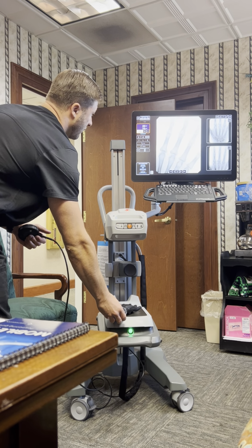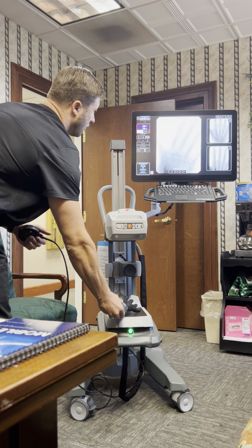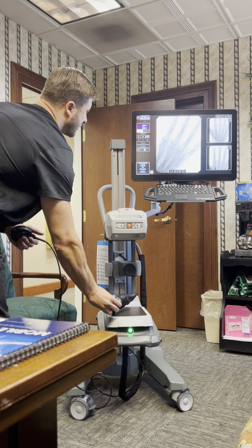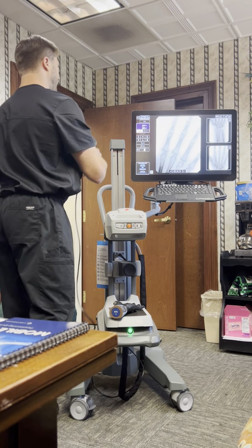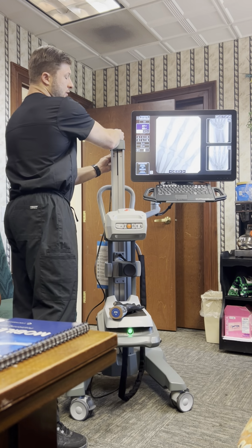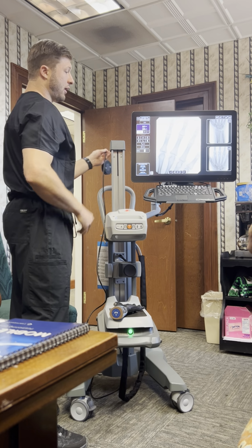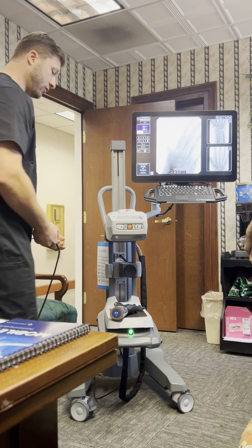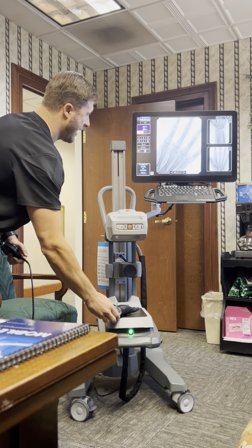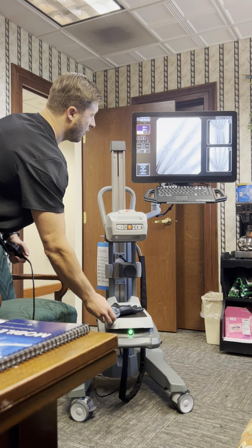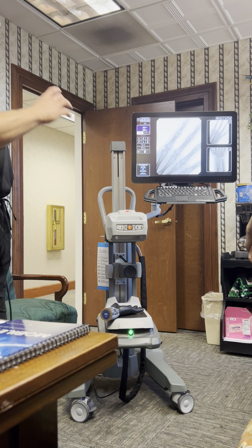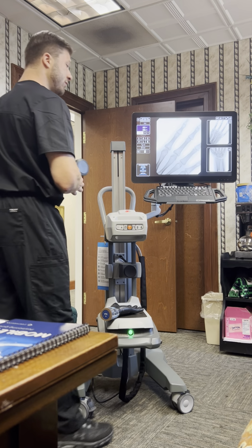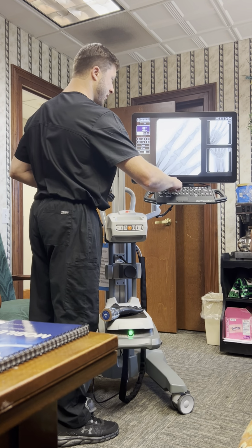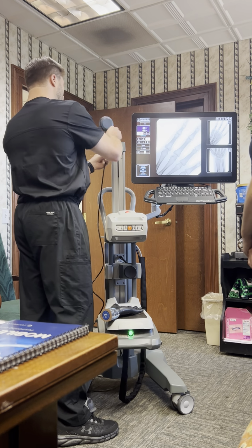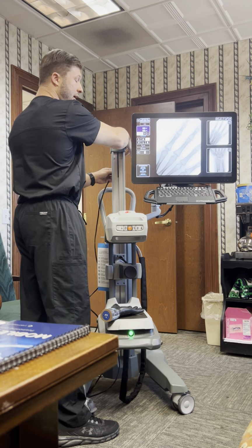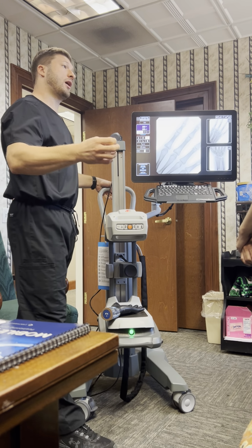So if we were to just go here with it, we can go here and then down, for example. So now it's just going to play on this continuous loop for us, right? If we do not hit DVR, we can still utilize live fluoro. So watch this. We could navigate to a specific joint space, but it's just going to capture that last frame of the image. Just keep in mind, in order to record fluoroscopy, DVR needs to be enabled. However you manipulate the image, however you filter the image, it will send to PACS that way too.